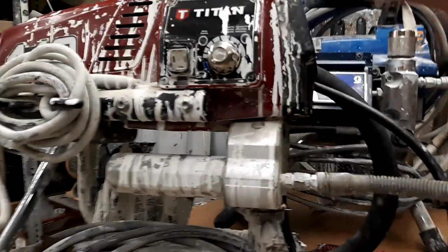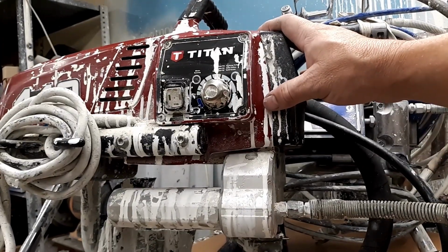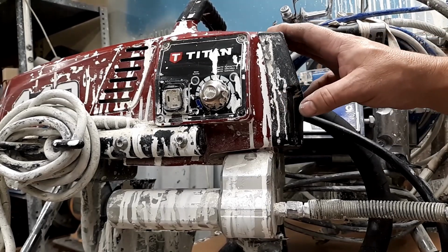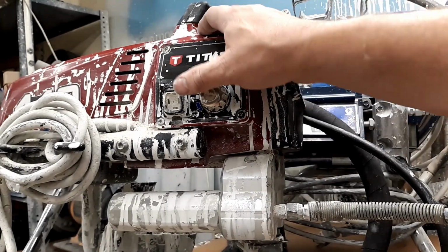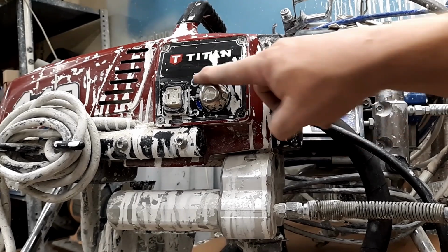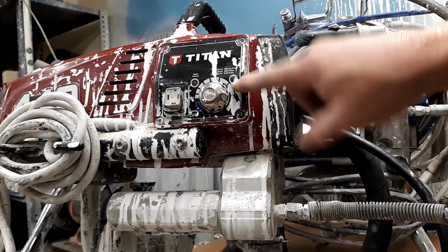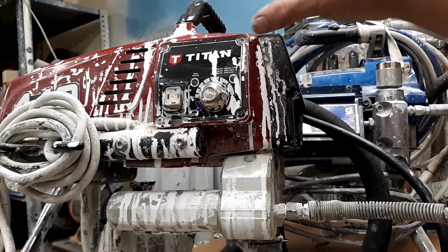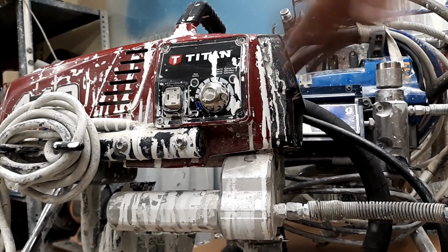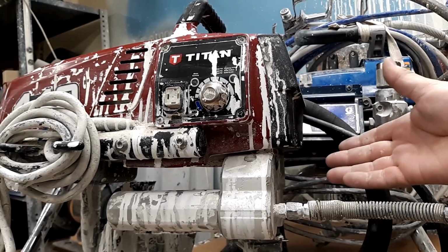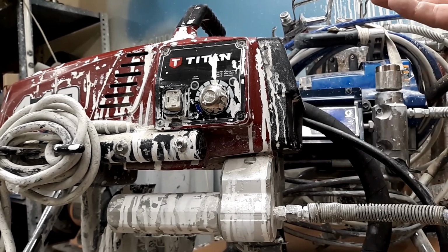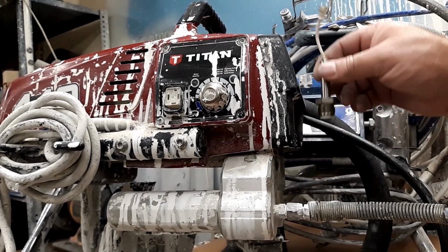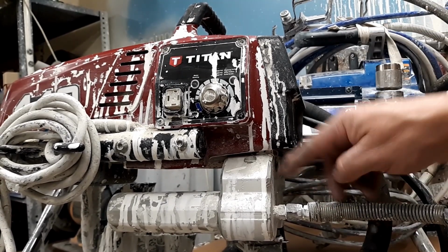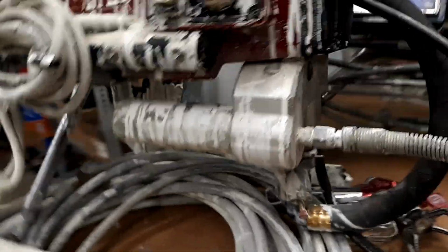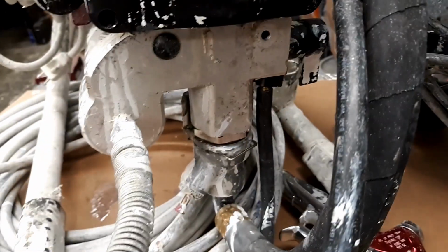So first thing you're going to do, let it warm up and thaw out. After it thaws out for about 24 hours where it's warm, you're going to plug it in and turn it on. Watch your lights. If it's a steady yellow light and no motor is running, that means more likely you got a transducer. If it starts running, then you want to check your pressures. If the pressures are exceedingly high, then it's going to be a transducer. Once you've got that addressed, you start building pressure, you start looking for leaks. If you don't see any leaks, then more than likely you don't have an issue.